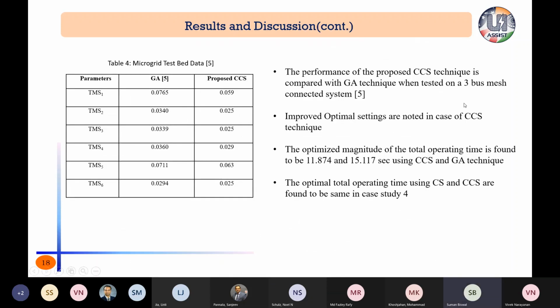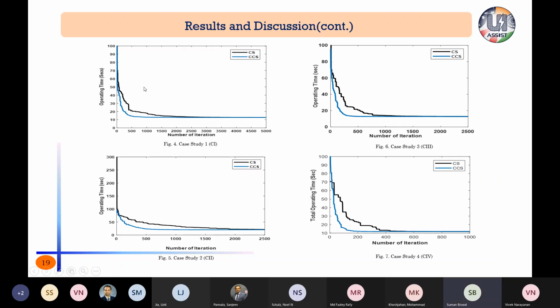Similarly, it is also tested on a small system, a 3-bus system, taken from the literature where the genetic algorithm, another optimization technique, is used. It is found that the proposed CCS is capable of generating a better solution: the total objective function value is 11.874, whereas the GA technique provides 15.117. These are the convergence characteristics of the objective function, compared with the original cuckoo search. Up to this point we have considered the standard operating characteristic of the relay, that is, beta is 0.14 constant and alpha is 0.02. We compared them, and the chaotic cuckoo search gives an improved solution compared to the original cuckoo search algorithm, and the convergence characteristics are also better.